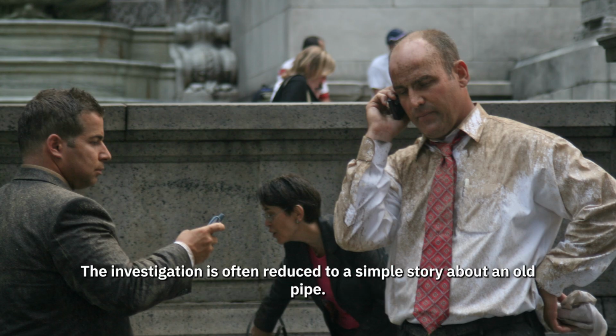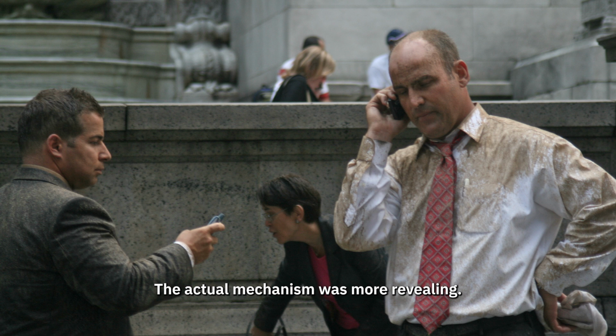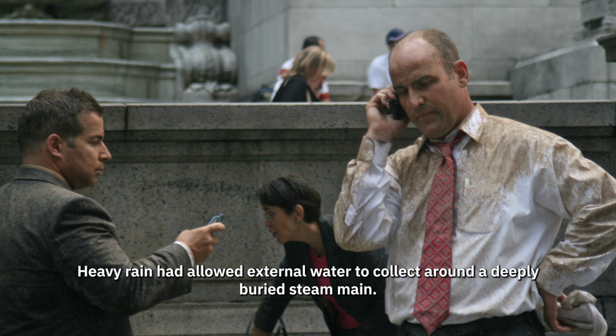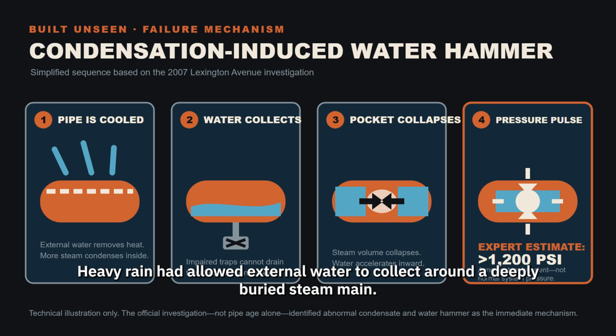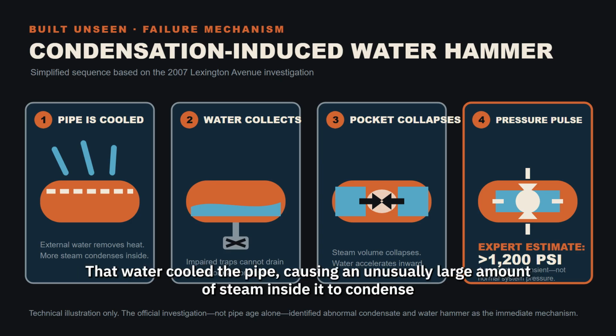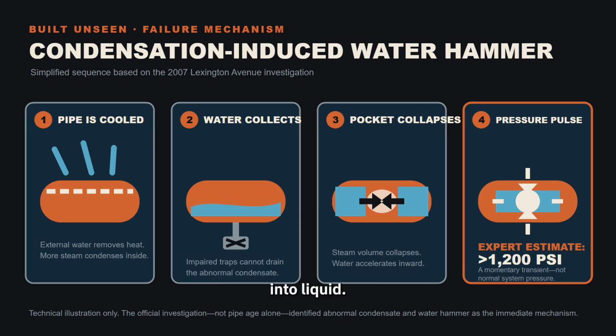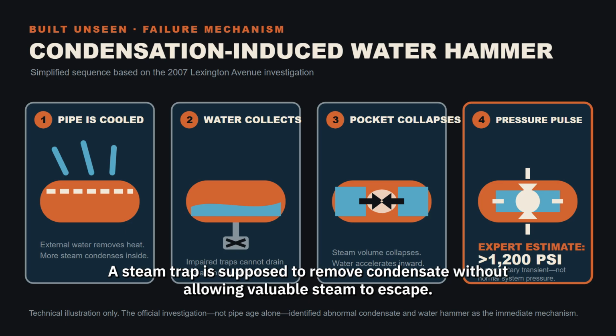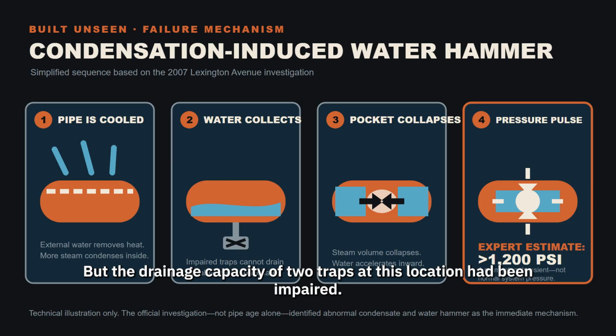The investigation is often reduced to a simple story about an old pipe. The actual mechanism was more revealing. Heavy rain had allowed external water to collect around a deeply buried steam main. That water cooled the pipe, causing an unusually large amount of steam inside it to condense into liquid. A steam trap is supposed to remove condensate without allowing valuable steam to escape, but the drainage capacity of two traps at this location had been impaired.